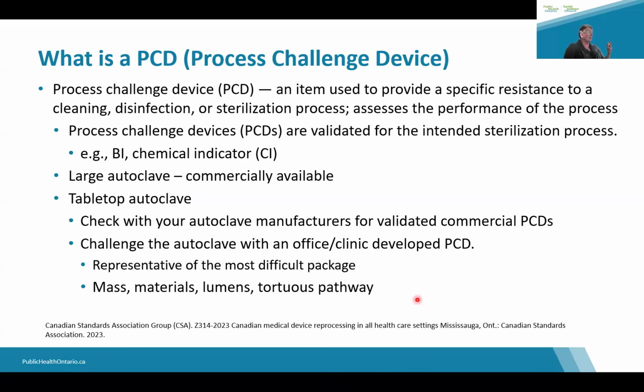So what is a process challenge device? So here's the very standard formal definition. It's an item used to provide a specific resistance to cleaning, disinfection, or sterilization process to assess the performance of that particular process. So process challenge devices are validated for the intended sterilizer. Depending on which sterilizer you have, you would use a PCD that was validated for use on that sterilizer. And you can have a biological indicator or a chemical indicator inside of the PCD or both. It depends on the situation.